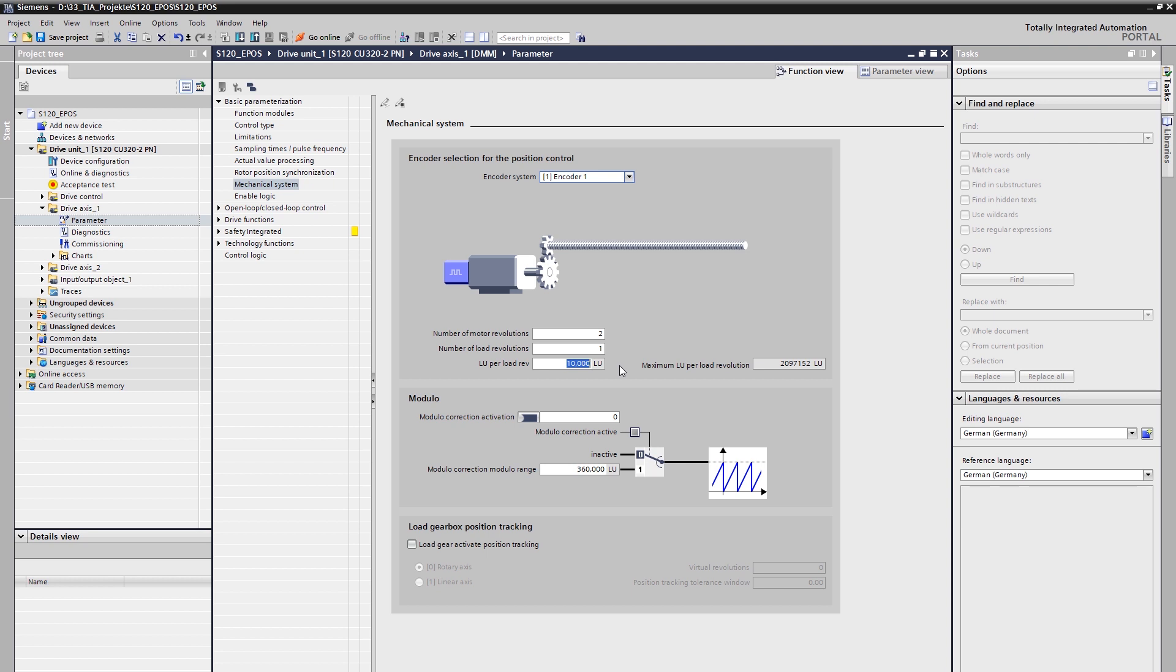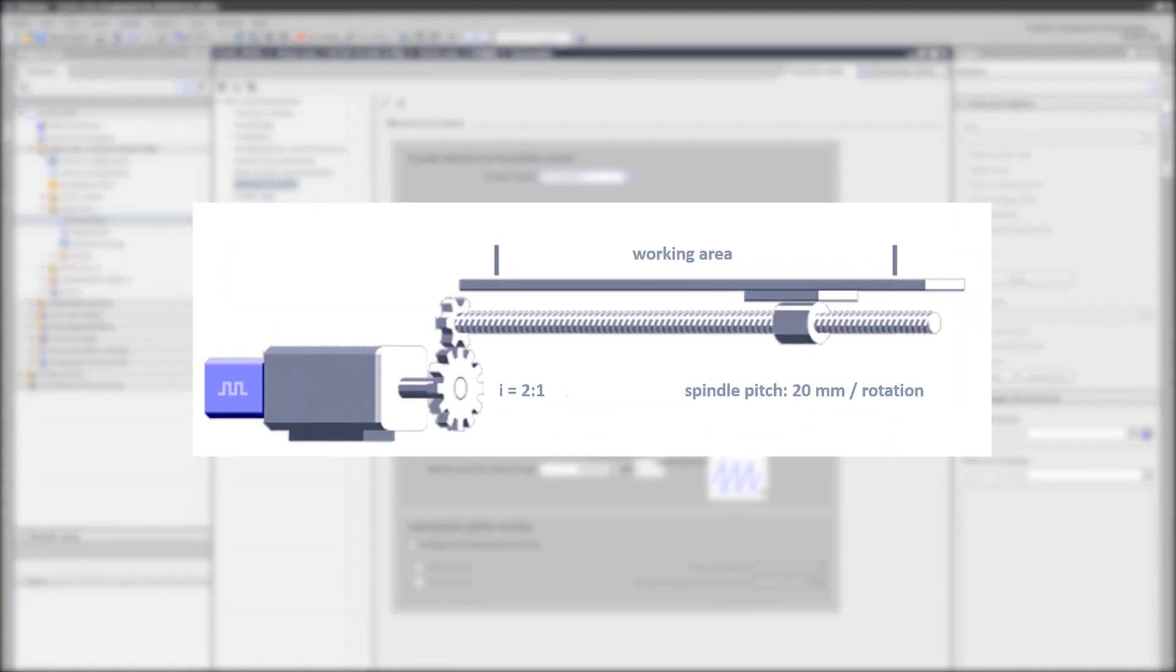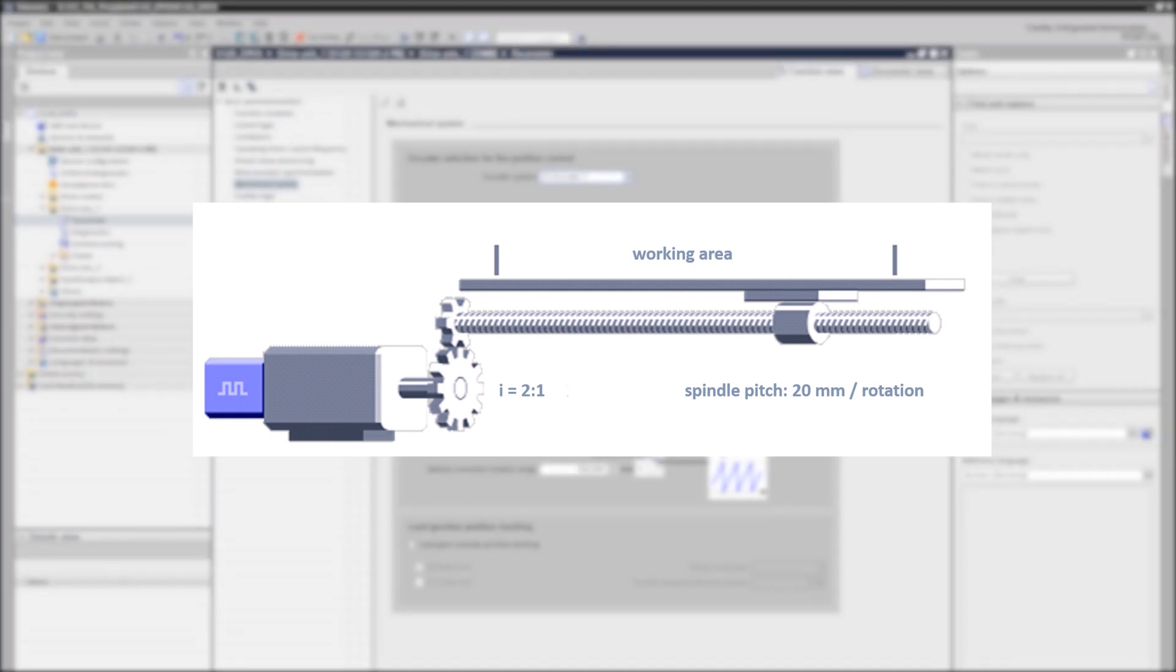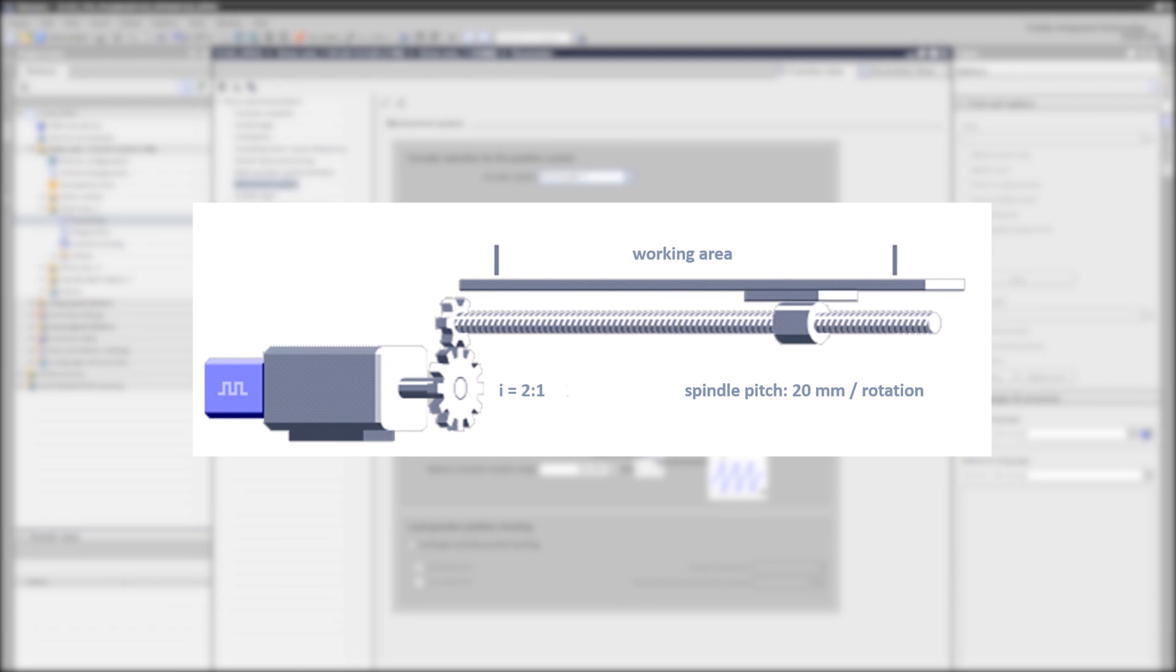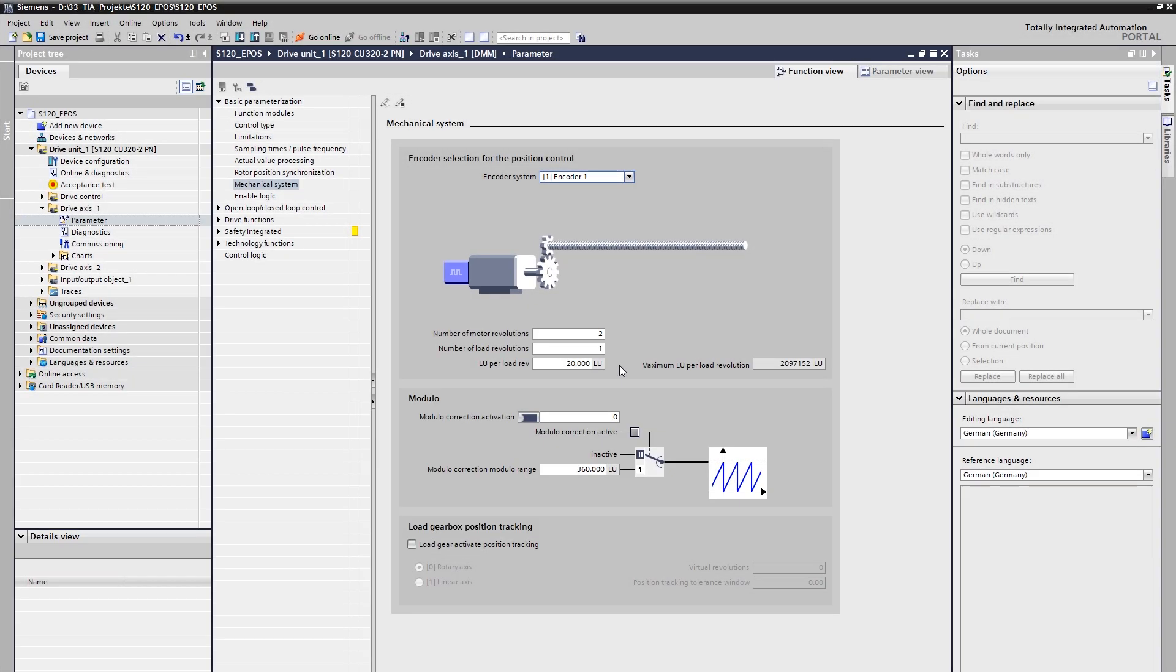Since we can freely define the unit of measurement for our movement, we set ourselves to millimeter for the linear mechanics. In order to be able to position as accurately as possible, a resolution of thousandths of a millimeter has proven itself. This means one micrometer corresponds to a neutral length unit of one LU, or in other words, one millimeter corresponds to 1000 LU. In our example with a spindle pitch of 20 millimeters per revolution on the load side, this corresponds to 20000 LU per load revolution. The gear ratio does not have to be taken into account here, since the load side is always considered for position control. We can therefore remember that we always specify position set points in micrometer, since one LU now stands for one micrometer in our project planning.